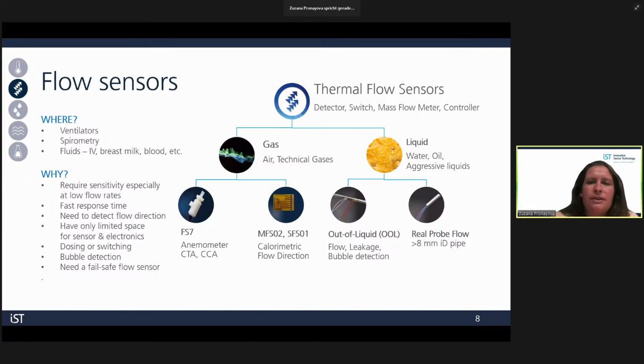Thermal flow sensors serve in medical devices as mass flow controllers, meters, or simple switches. You find them in commonly discussed ventilators, as well as breathing gas analyzers or spirometers. We also see an increase in applications with different fluids where the sensor can be integrated into the disposable part. The reason thermal flow sensors are the go-to solution is often their sensitivity at low flow rates and a simple, robust assembly without any moving parts.